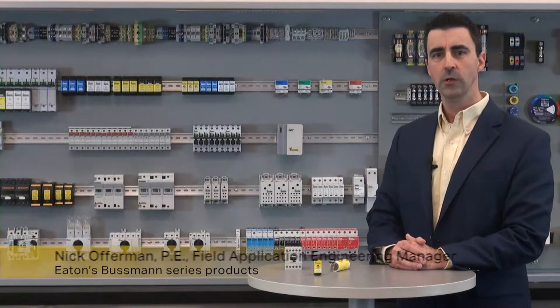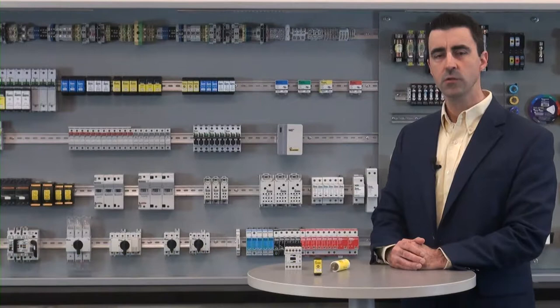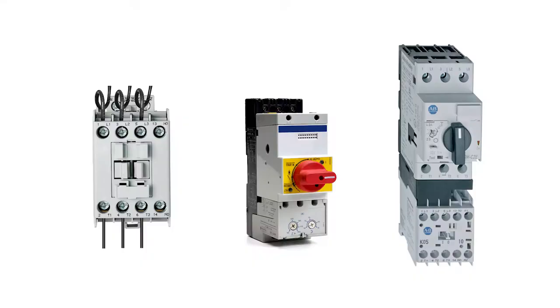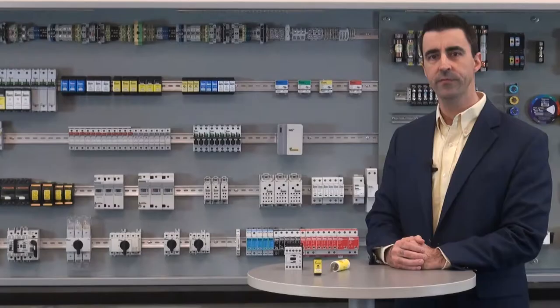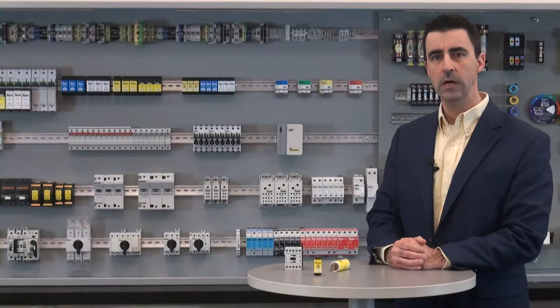Current limitation plays a major role when protecting components and achieving a high short circuit current rating. Electrical components such as contactors or motor starters have a standard fault rating or default short circuit rating and sometimes a higher rating called a high fault rating. This high fault rating requires a specific class of fuse and max amp rating to achieve the higher level of protection.